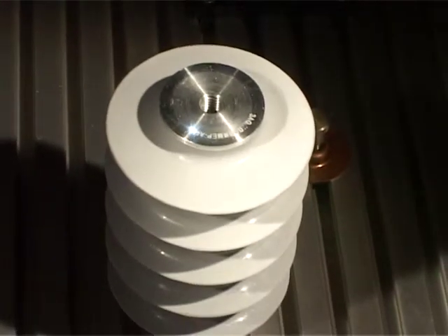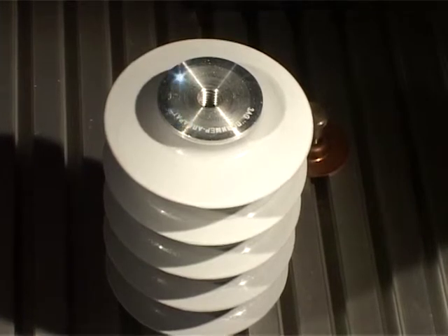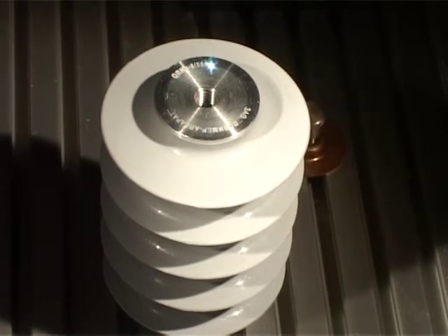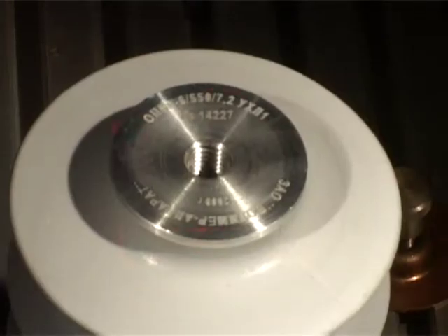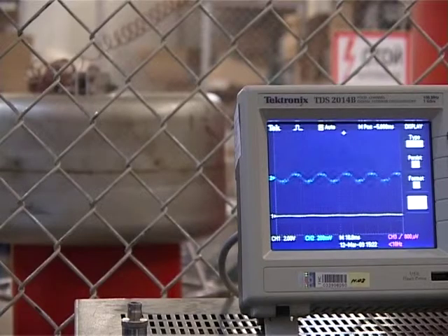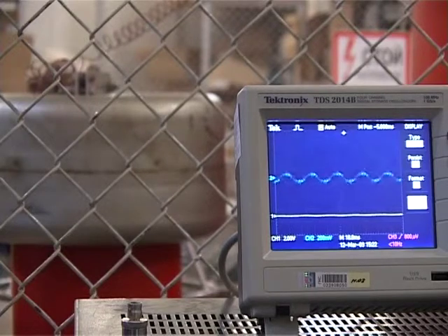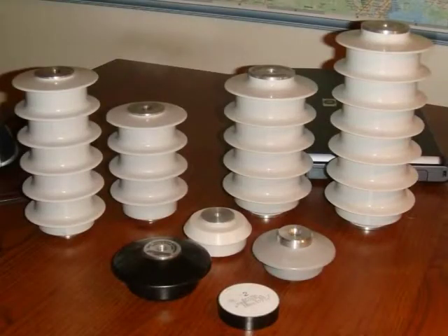Application of rubber directly on the arrester flange and usage of adhesive composites ensure design hermeticity. Housings of category 2 overvoltage arresters are made of glass nylon composite directly on the thermoplastic automated machine. Type, serial number and date of manufacture are indicated on each arrester. All arresters are subjected to acceptance tests, then packed and shipped to the customer.